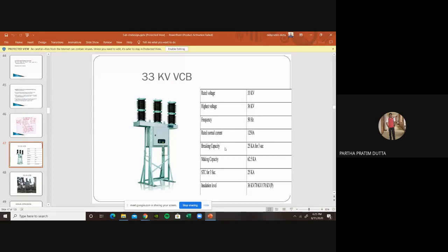What is the making capacity? Making capacity is the maximum current that the breaker can conduct at any instant of closing. It is considered as the peak value of the first cycle when there is a short circuit between the phases. Suppose there is a short circuit between the phases. In that case, whatever current flows, that also can be withstood by this VCB system. That is called the making capacity. That is a standard parameter. Obviously, the short circuit current 3 second withstand is 25 kA, and the insulation level is, as I told earlier, 36 kV, 70 kV, and 170 kV pulse.